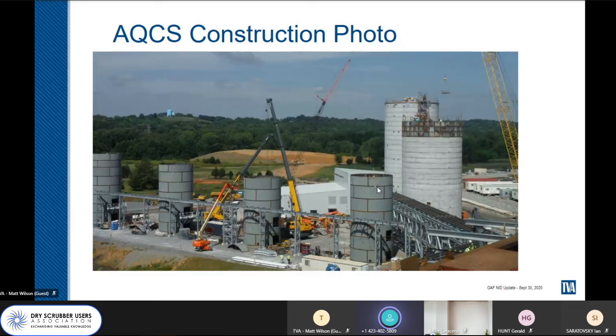And then each day bin is also sized to store 30 hours of pebble lime. So this really adds up over the days, and that is full load operation for that full 30 hours, which in reality does not happen that often. We run full load and then we can run low load. And of course you can always run low load if you run into a supply issue to stretch out your storage capabilities.